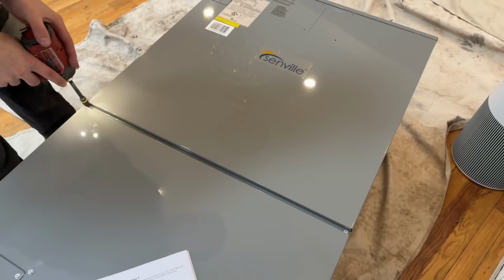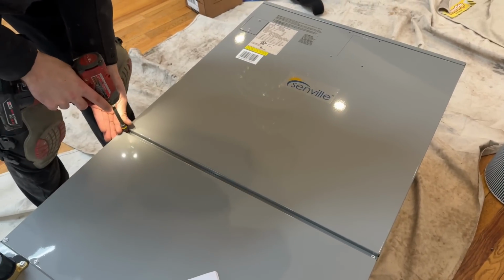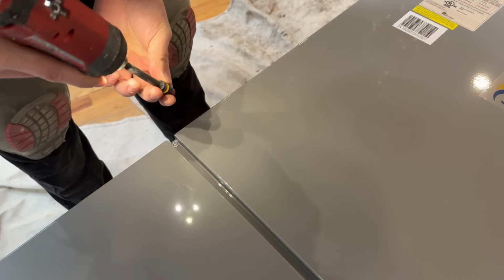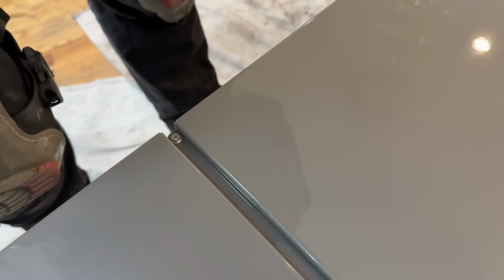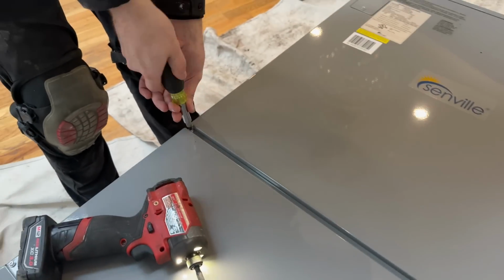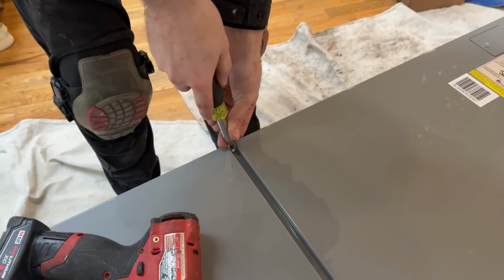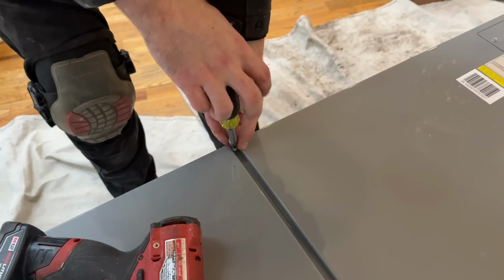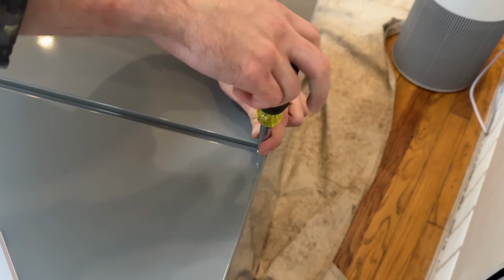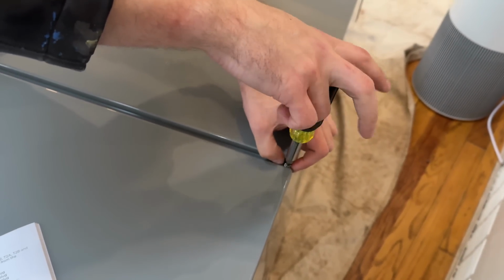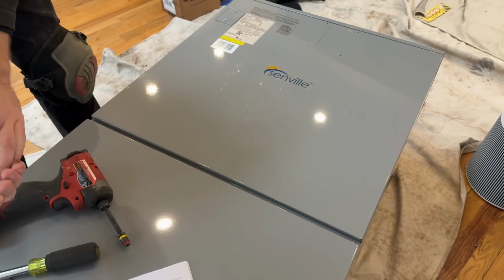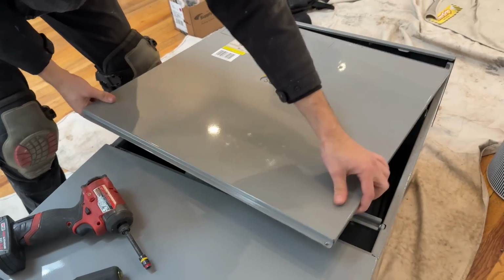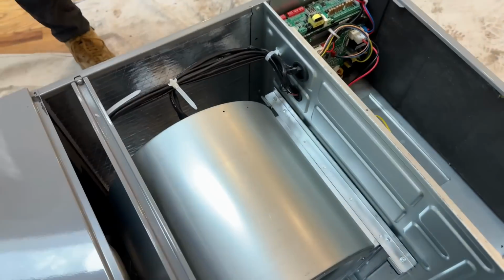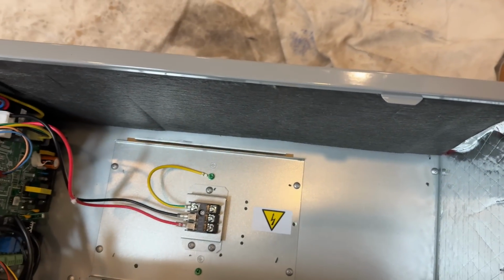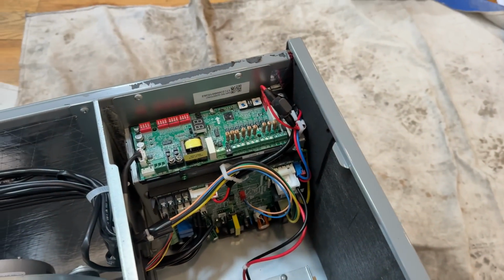Step 2, remove upper cover assembly. That's weird. It would be nice if we were able to get our 1/4 inch and 5/16 Malco driver in there, but it is what it is. Okay, remove that upper cover assembly. Beautiful. Exposing the blower compartment, optional electric coil, control boards.